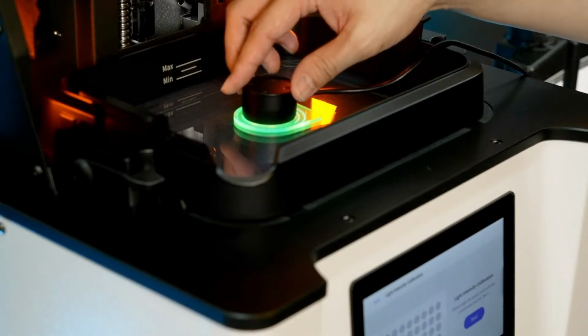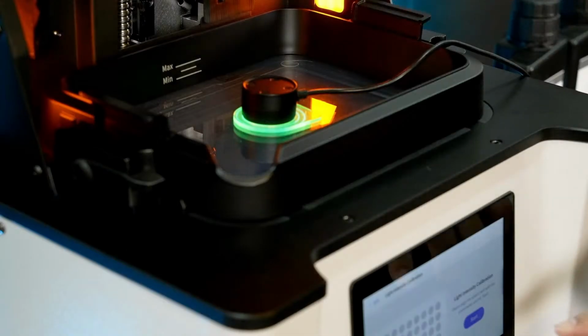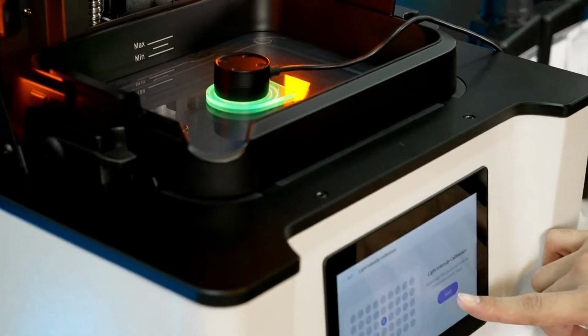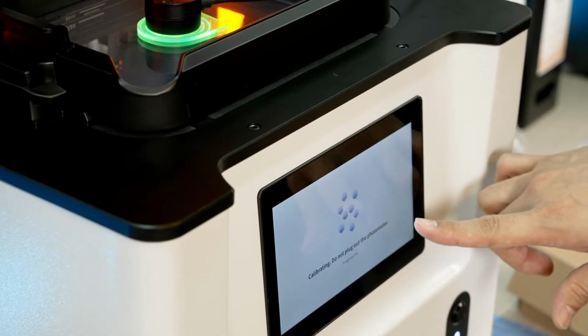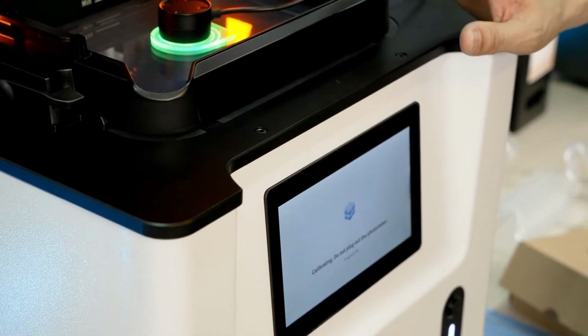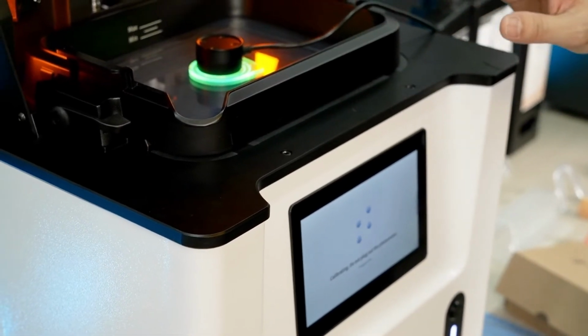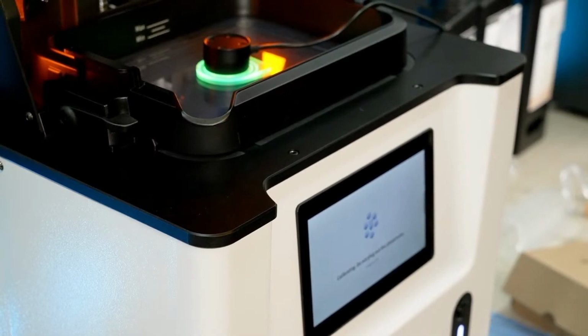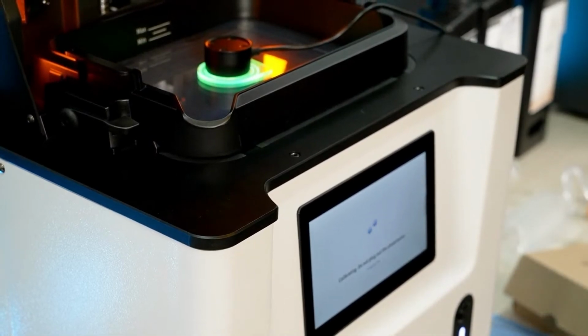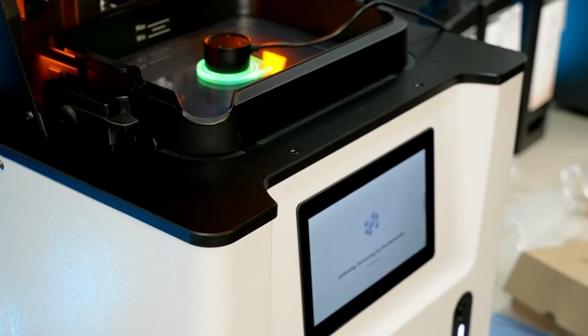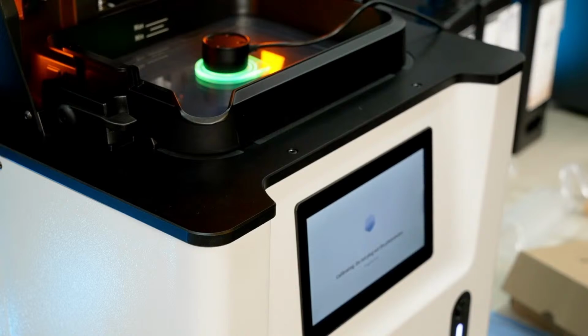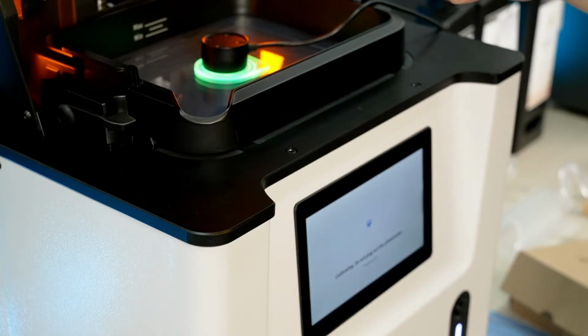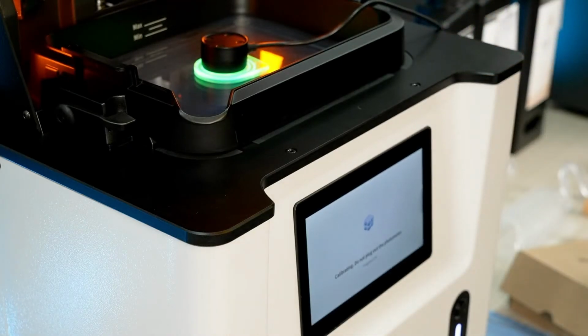Right now you can put your photometer in the center of the light spot, and for the light intensity calibration, you can hit the start button right here. After hitting the start button, please do not move anymore, and it will do the calibration automatically for you. And during the operation, please do not look directly at the UV source with your bare eyes. Please wear sunglasses or something to protect your eyes.